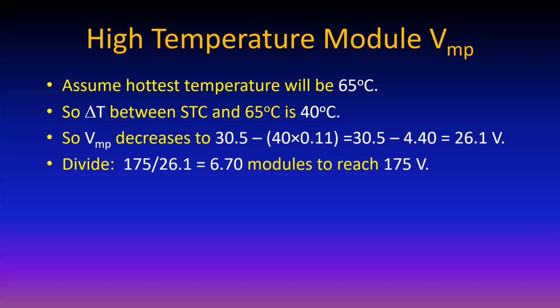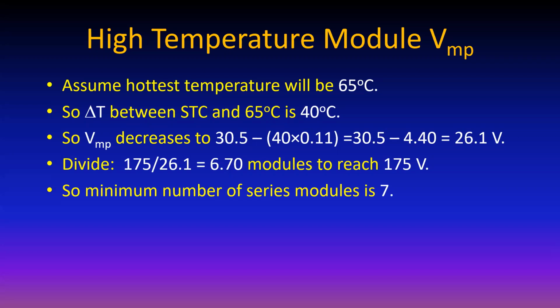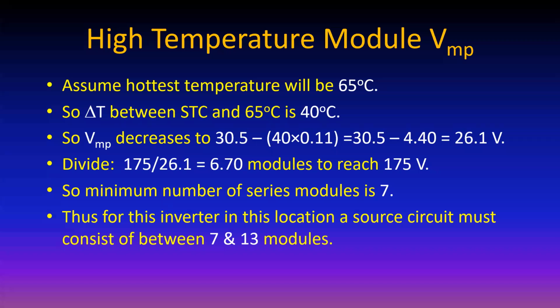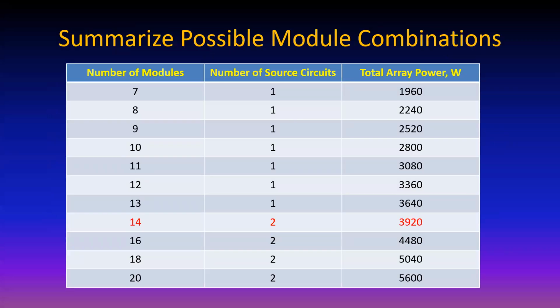Plug that in, 175 is the minimum value you want for that string voltage. So divide that by 26.1, gives you 6.7. This time we round up because anything under 6.7 gives us too low of an output voltage, so we have 7. So that means in this string, we can have anywhere between 7 and 13 modules, and the inverter will be perfectly happy because the voltage range of the output of those in series will fall within inverter input specifications.